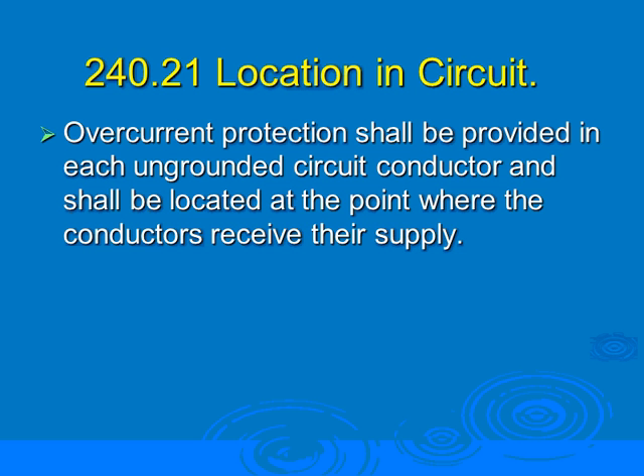So, not the load. Technically, I can have a 100 amp fuse connected to a number 1 conductor and tapped from it with a number 14, as long as I can prove that the number 14 conductor will survive short circuit and ground fault conditions. Basically, it's not going to melt.